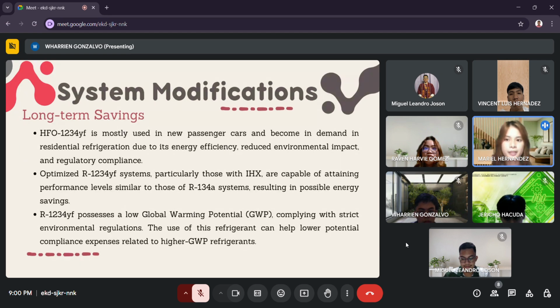In terms of long-term savings, first, HFO1234yf is mostly used in new passenger cars and is becoming in demand in residential refrigeration due to its energy efficiency, reduced environmental impact, and regulatory compliance. Second, optimized R1234yf systems, particularly those with IHX, are capable of attaining performance levels similar to those of R134a systems, resulting in possible energy savings. And the third one, R1234yf possesses a low global warming potential, or GWP, complying with strict environmental regulations. The use of this refrigerant can help lower potential compliance expenses related to higher-GWP refrigerants.